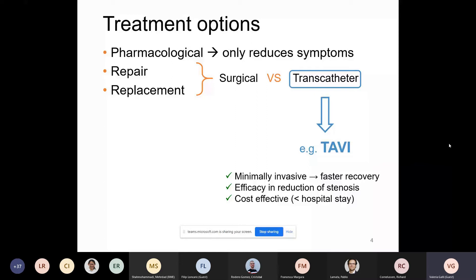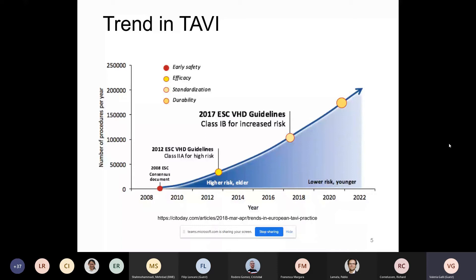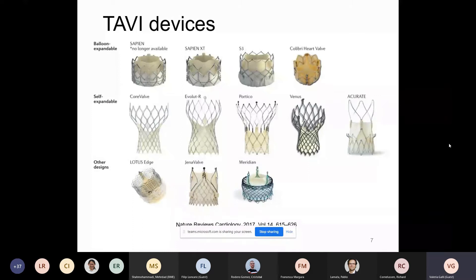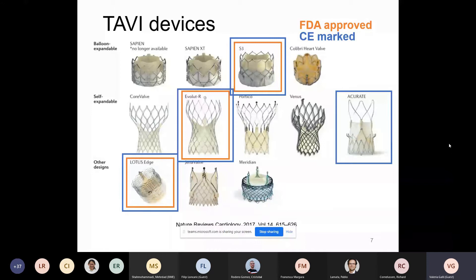The trend in Europe — this is data from the European Society of Cardiology — tells us that from the early days when only higher-risk or inoperable patients were sent for TAVI, today lower-risk and younger patients are treated, which poses new challenges for the devices. There is a plethora of devices on the market, both in clinical studies and available commercially. There are three main designs: balloon expandable, self-expandable, and other designs. Some are approved in the US and others in the European Union, and the market is dynamic — for example, the Venus valve in China.